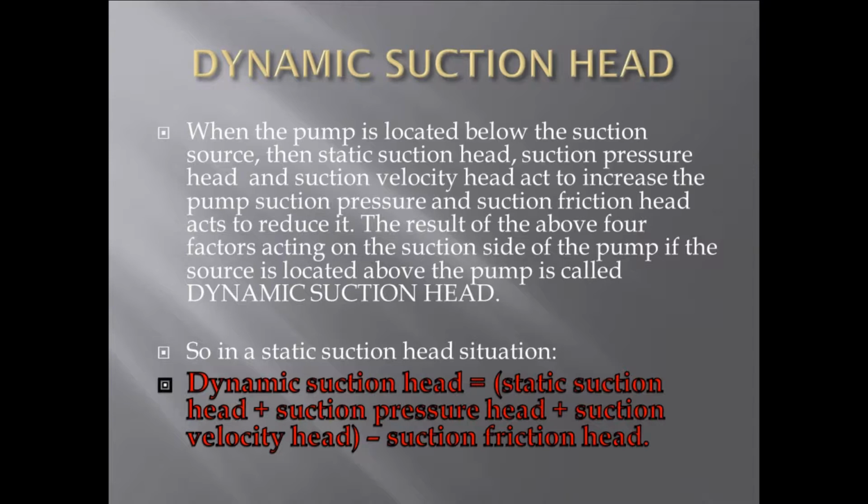So in a static suction head situation, dynamic suction head equals static suction head plus suction pressure head plus suction velocity head minus suction friction head.